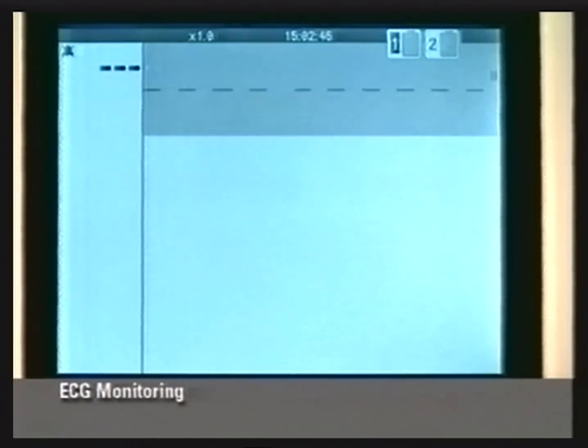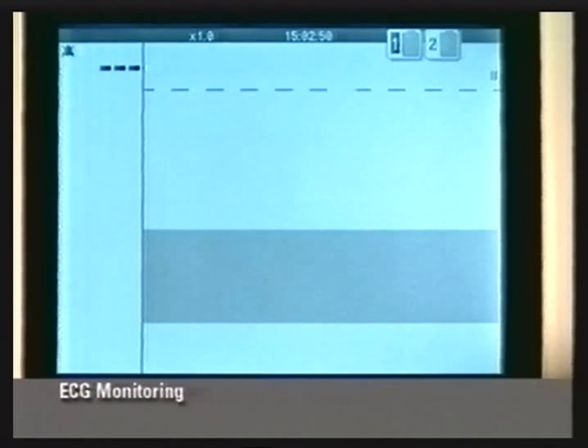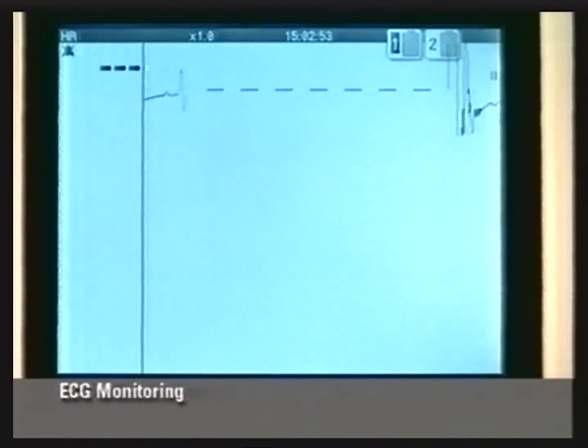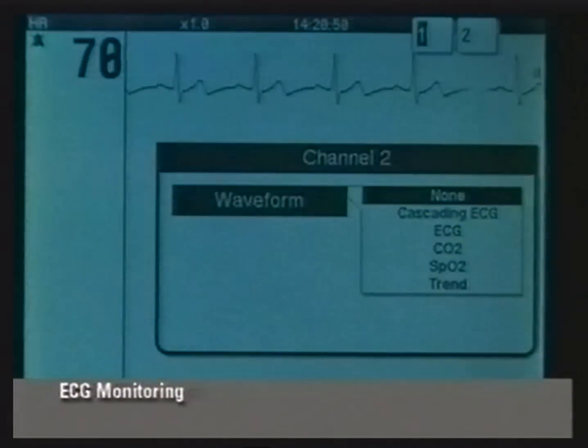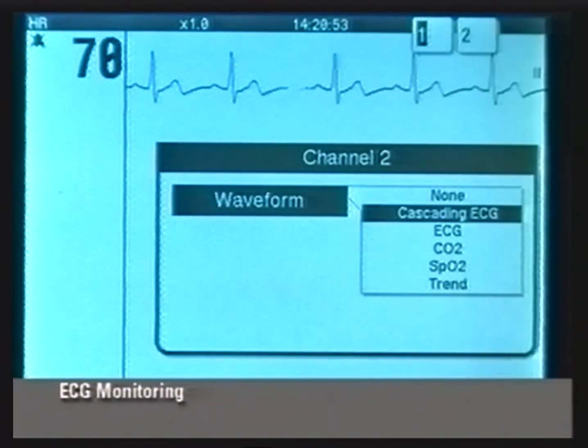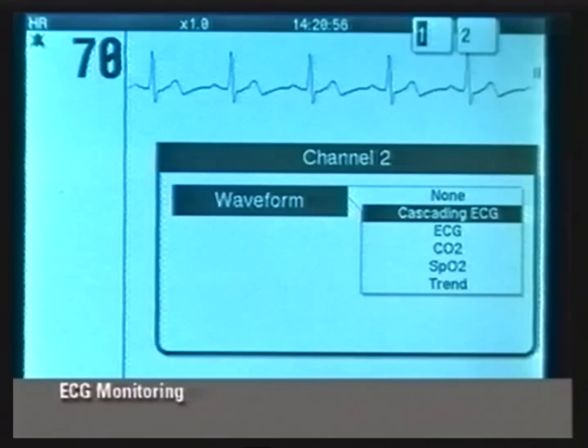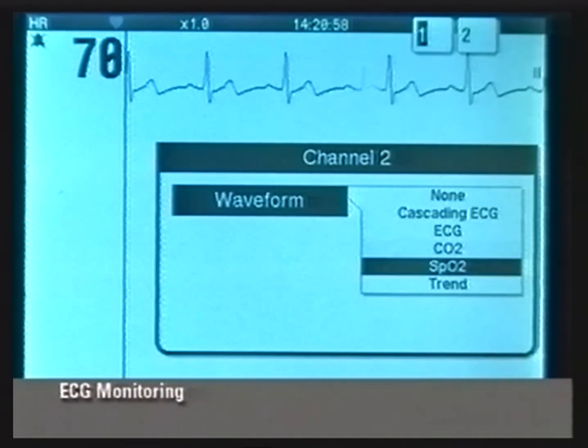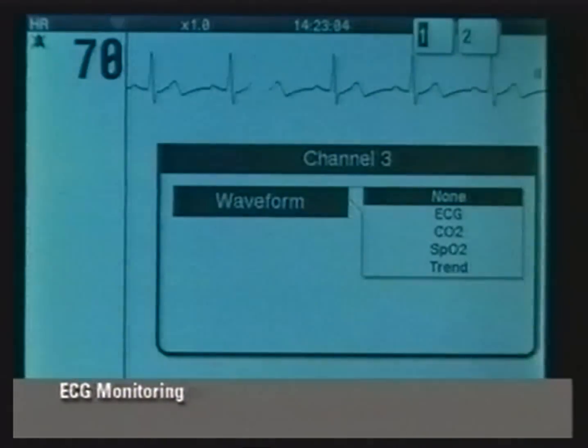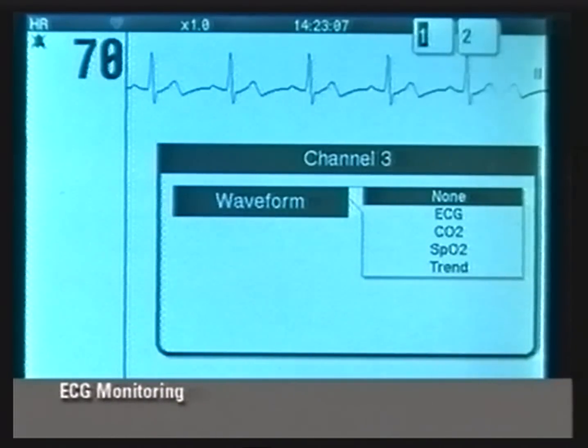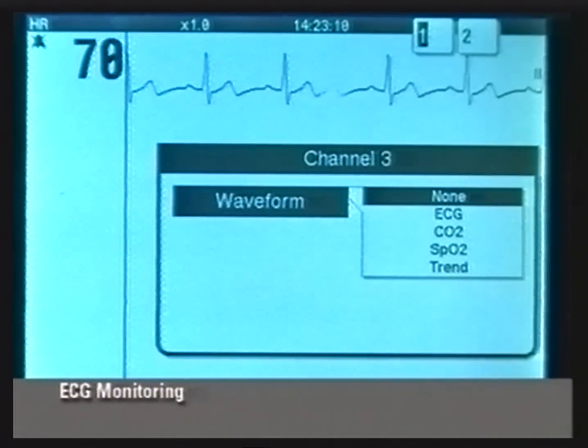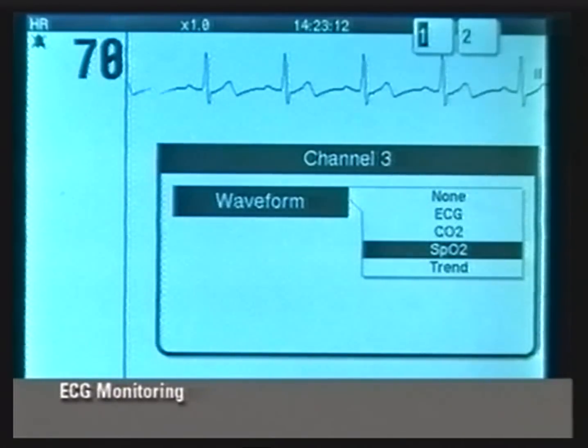The Lifepak 12 defibrillator monitor screen can display up to 3 waveforms. The top waveform area is called Channel 1, the middle area is Channel 2, and the lower area is Channel 3. The ECG always displays in the top channel when the defibrillator is on. Channel 2 may be left blank or display a continuation of the Channel 1 ECG or one of the other monitoring parameters or a trend graph. Channel 3 is available only if a 100mm printer is installed. It may be left blank or display a different waveform or a trend graph.